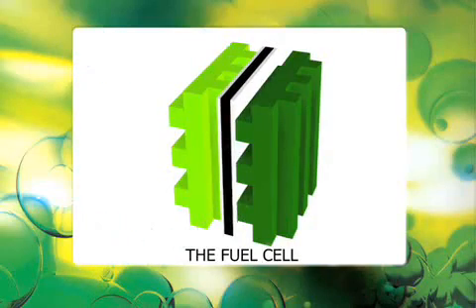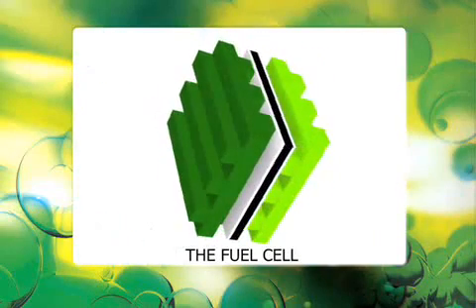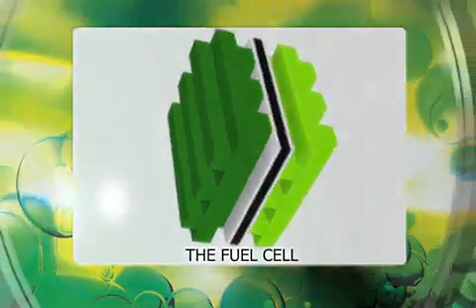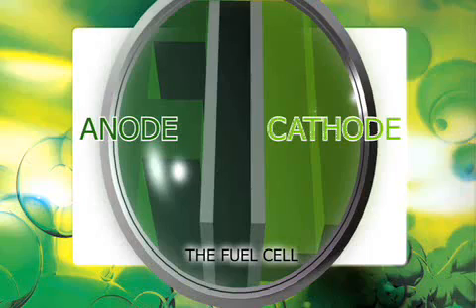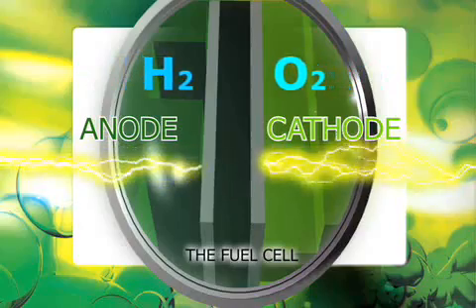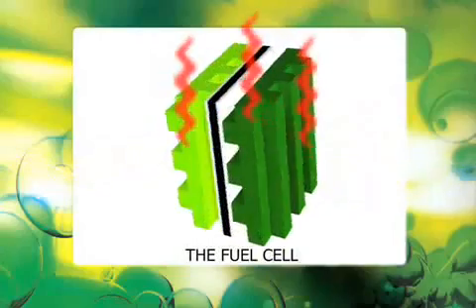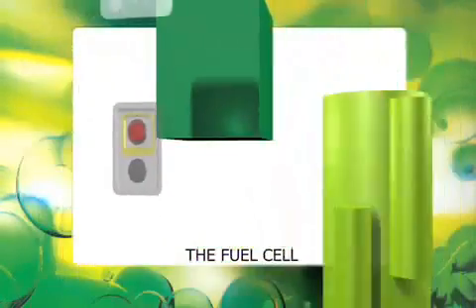The Voller Emerald system's electronics carefully feed hydrogen and air into the fuel cell in order to create a controlled electrochemical reaction on the fuel cell's special membrane. The membrane is a thin, flexible film that is coated on both sides with a catalyst layer. One side is the anode and the other is the cathode. When hydrogen is fed to one side and oxygen to the other side of this membrane, electricity is created. As well as creating a small amount of water, an important byproduct of this electrochemical process is heat.